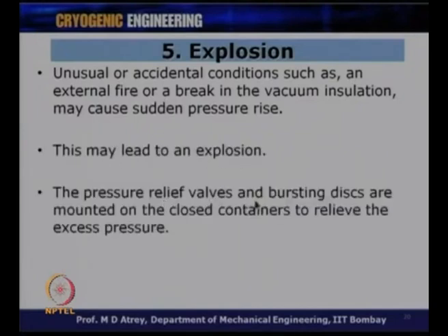The pressure relief valves and the bursting discs are mounted on the closed containers to relieve the excess pressure. These aspects are very important while dealing with the design of these cryo containers, and we will see in detail what relief valves and bursting discs are all about.